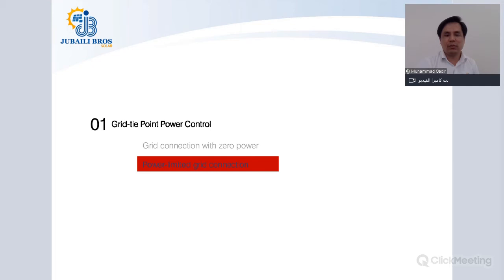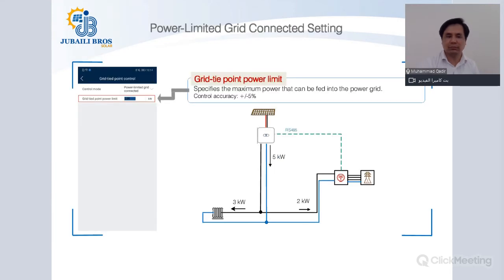We spoke of the two types of zero export, which are single phase and the total power limitation. We go ahead now with the next type of control, which is called power limited grid connection. Under the grid tie point control, you have the option of selecting the power at this point. The accuracy of this would be around plus minus 5%.